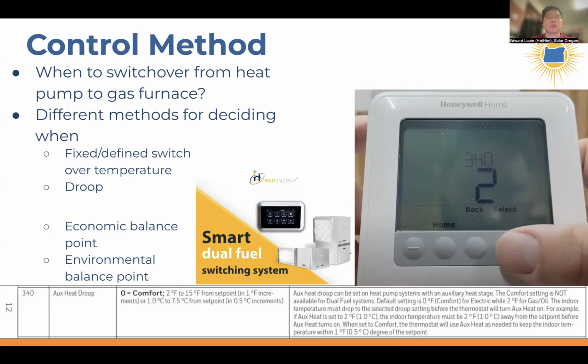The other common way to do it is to do something called droop. How droop works is that let's say you set your thermostat to 72 and the heat pump is running and running and running, but the temperature of your house keeps dropping even though the heat pump is running. Therefore the heat pump's not able to keep up. That would be an indication that the outside conditions are so cold that the heat pump can't keep your house warm. So droop is set up so that if it's 72 and the house keeps dropping and by the time it drops 2 degrees, for example, you set the droop to 2 degrees, then when it hits 70 degrees, you'll turn off the heat pump and start the gas furnace to heat your house.